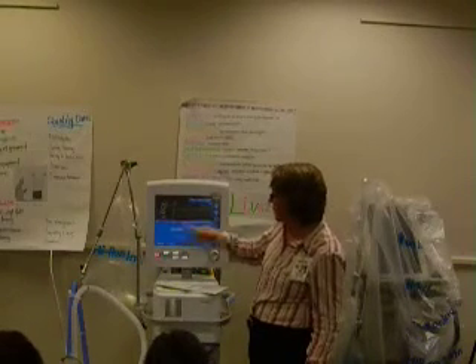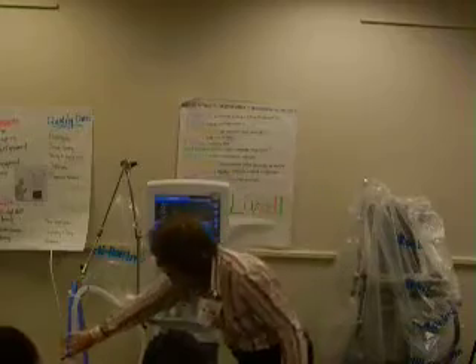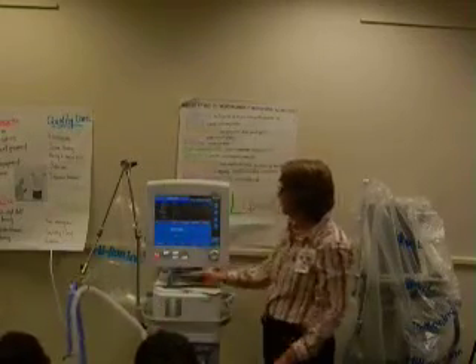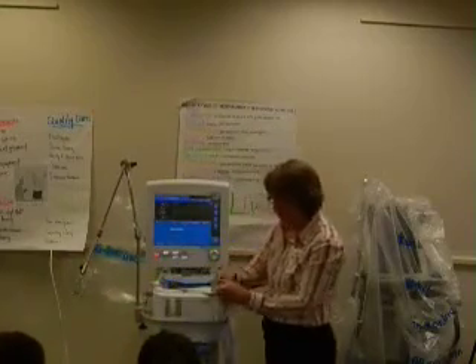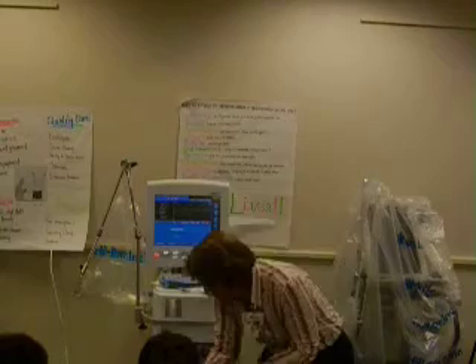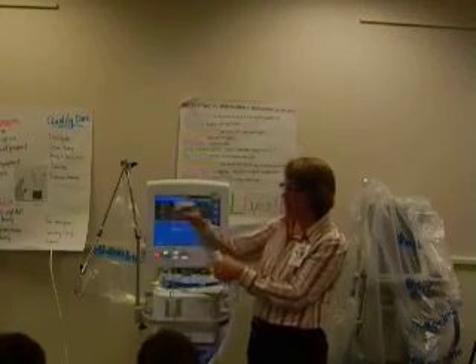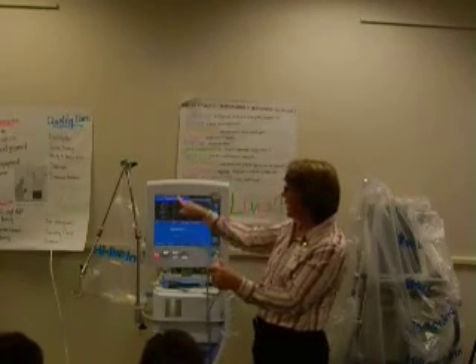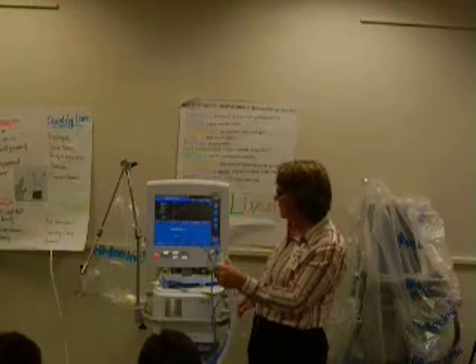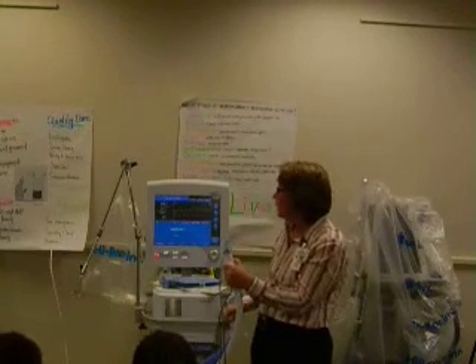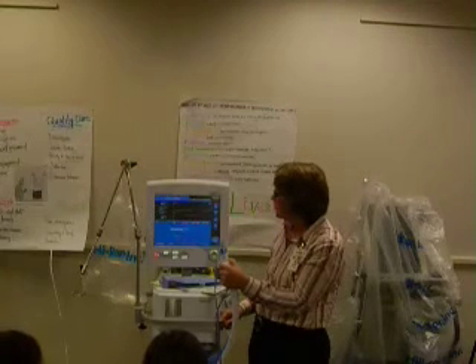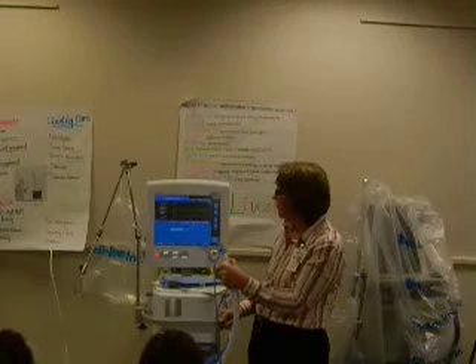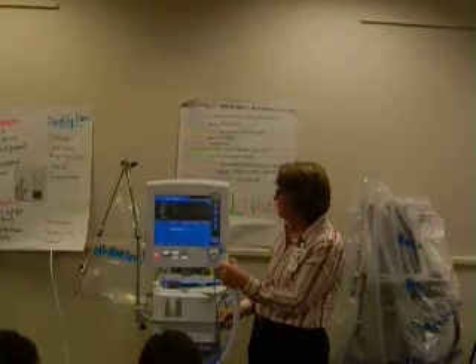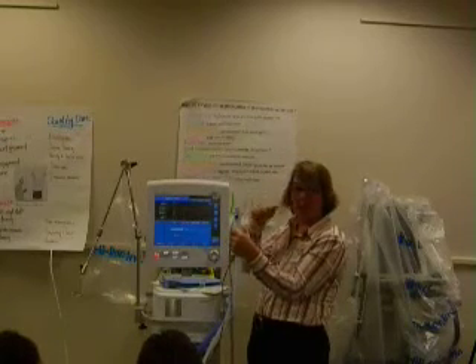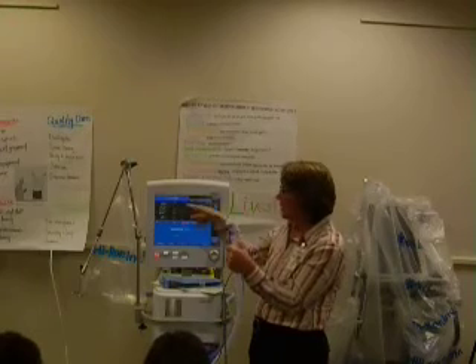So to do the flow sensor, you hit the button, flow sensor. It's going to say calibration in progress, disconnect patient. Turn the flow sensor. What it wants you to do is literally turn it so that the blue is not facing the patient, and now the blue is towards the vent circuit. When you do that, it'll automatically sense that and you'll see it'll keep going. You say calibration in progress. While you're doing this, you've got to watch what's in your blue bar there. Can you hear that? That's sending a different air through there that I was telling you guys about, and it's measuring to make sure that it puts the right amount. That's registering the right amount that it's putting through.